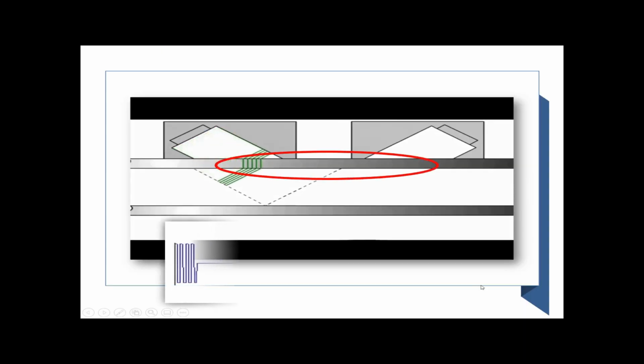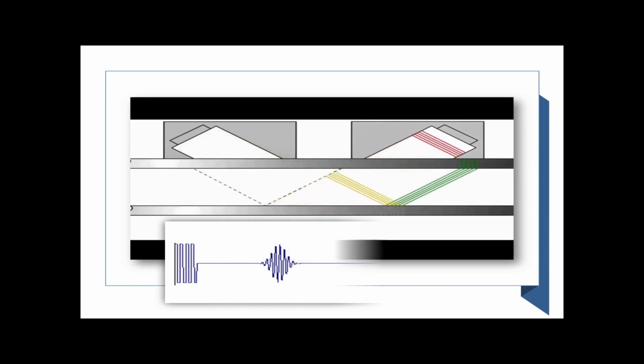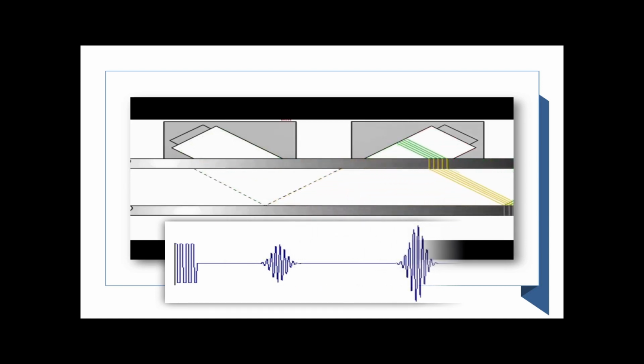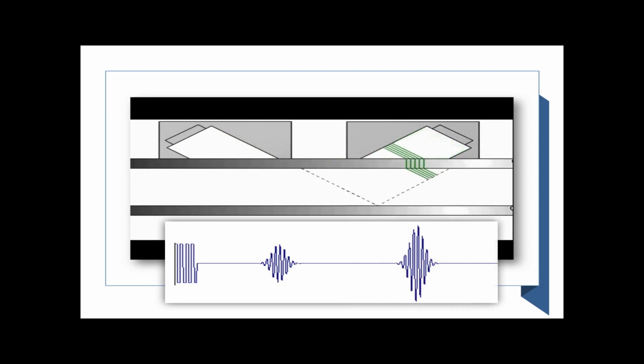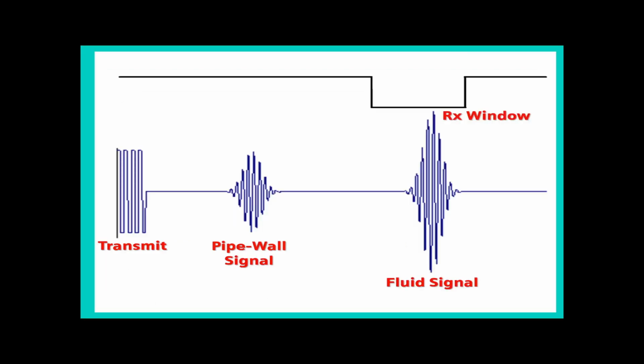As we saw, the pipe wall signal travels much faster and a shorter distance than the fluid signal. Therefore, it arrives at the receive sensor first. The fluid signal travels a greater distance, arriving much later. Normally, the flow meter will ignore that early pipe wall signal by electronically blocking it from detection. It does so by positioning its detection or RX window where the theoretical fluid signal should arrive. This prevents detection of the pipe signal.